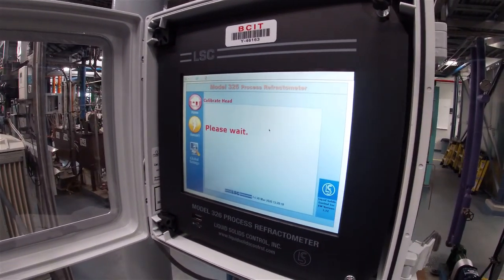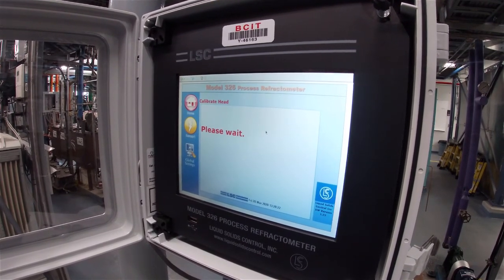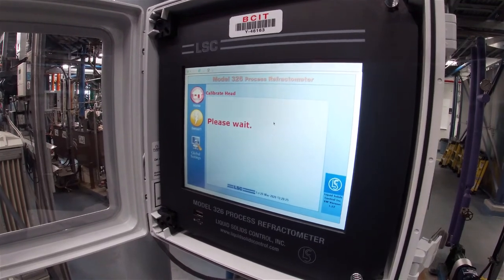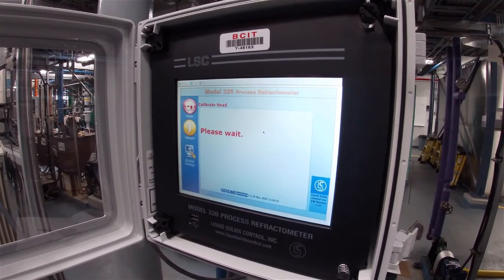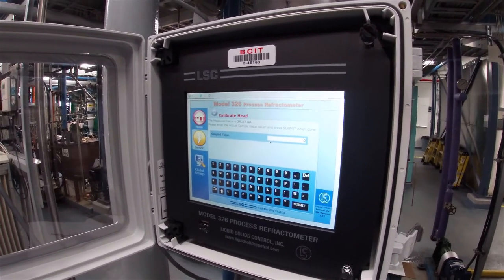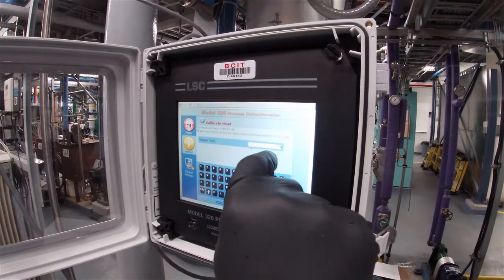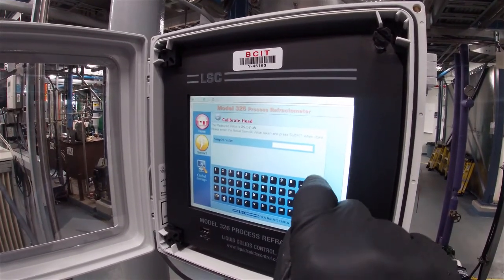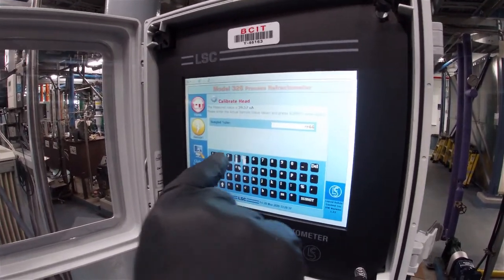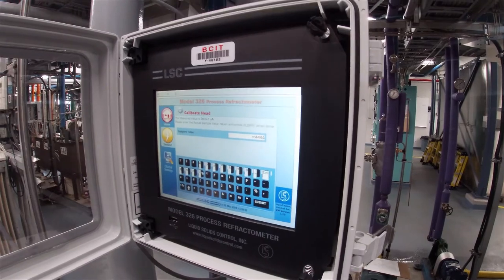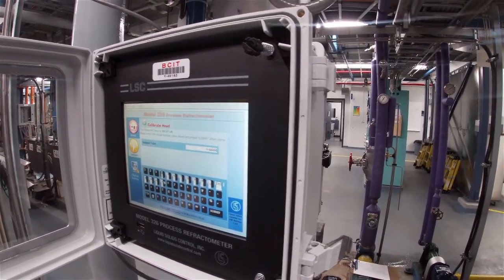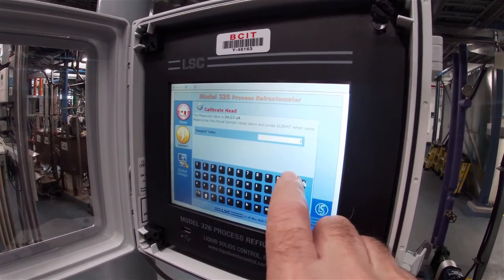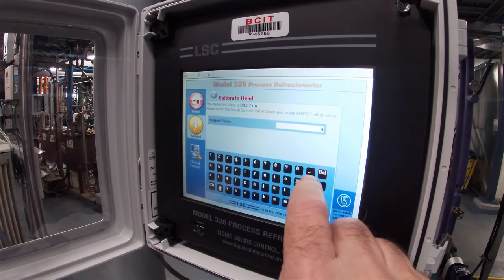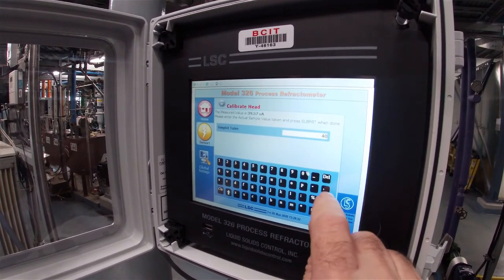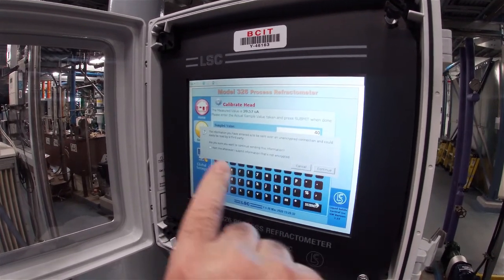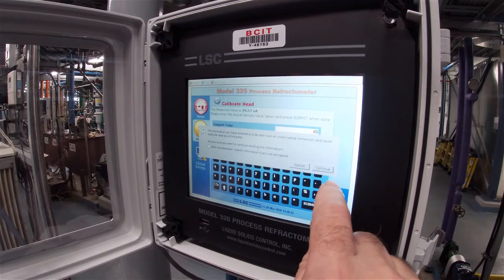And now it's waiting as it goes out and gathers the data for this calibration point. Hurry up and wait. Okay, so now it wants me to enter the sample value. That was 40%. I deleted the 0 that was on there. I put in a 4. The gloves are not helping me one bit. So now we're going to delete, and we're going to put in 4, 0. You don't have to put in the decimal point. Information is okay, continue.